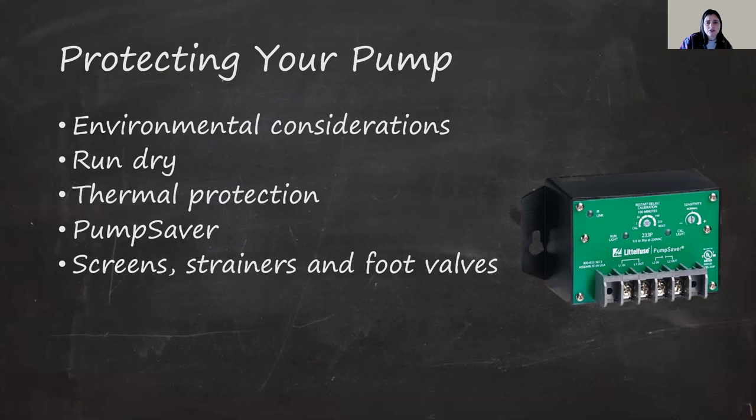A useful device I discovered was something called the pump saver. This device is wired in line with your pump and monitors the current voltage and power consumption. Once you've calibrated the device, it will shut off the pump if there's a current decrease or surge, which protects the pump from dry running, jammed impellers, and over and under voltage conditions.